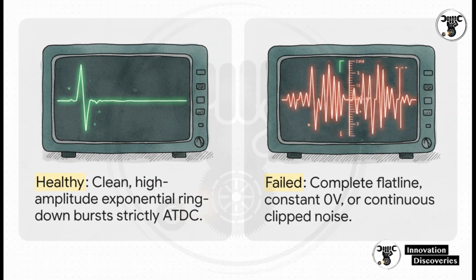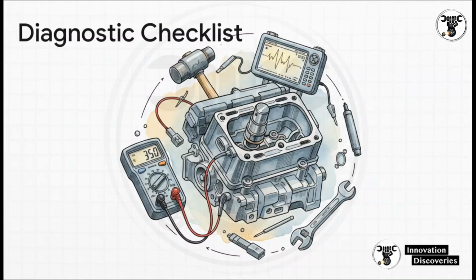You'll see a total flat line if it's an open circuit, a constant 0 volts from a dead short to ground, or just this continuous, ugly wall of clipped noise if the internal PZT element has shorted out against its own metal housing. The visual evidence is just undeniable. And here's something you really need to remember. Modern wideband sensors typically show an open loop on a standard digital multimeter, unlike the older resonant ones that would read a specific baseline between 3.3 and 4.7 kiloohms. So you literally cannot test them with just a simple continuity check.